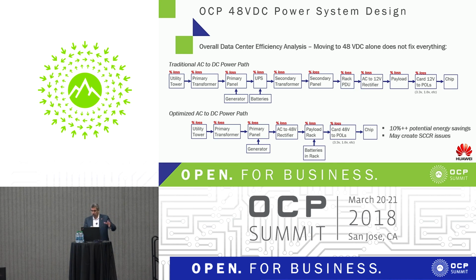You have a big improvement already with just using 48 volt, but if you follow this, this adds maybe an additional 10% improvement in energy savings to the whole system, because you've optimized the entire data center. And this is kind of like, we're looking at a macro and micro thing. Sure, there's advantages at the rack. There's also advantages at the data center, right? If you really think about it from all the way from the utility tower coming in, there's definitely an advantage of optimizing the whole flow of power, ending with 48 volt at the equipment.